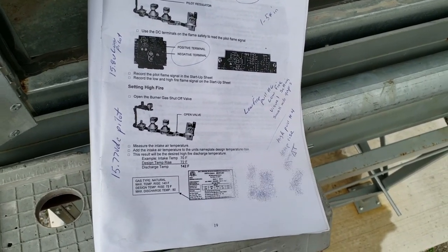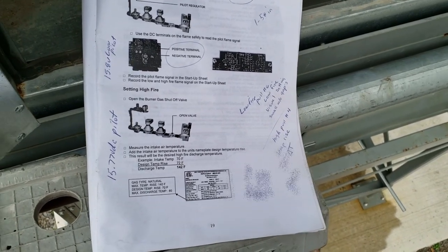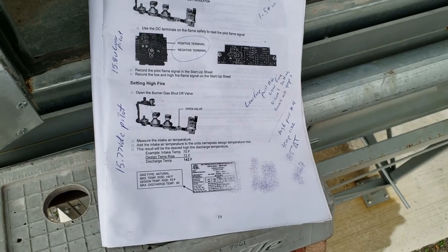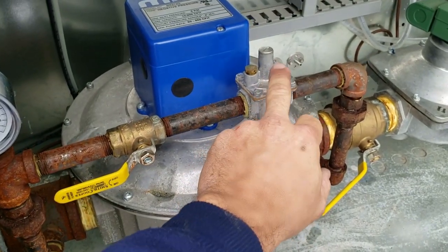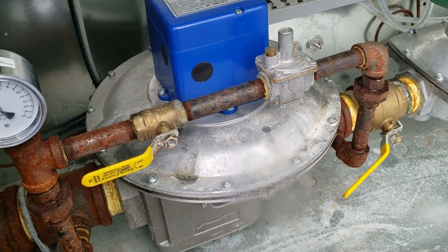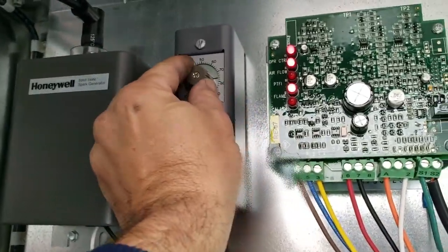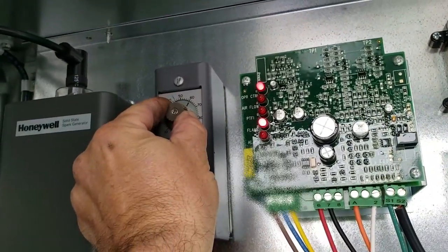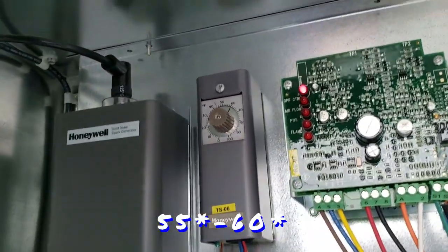So it's getting 70 degree air output even though it's turned all the way down. So you're going to have a little bit of something there. The bypass valve here is what's actually letting it through, and I've got it backed out as far as it can go. So a lot of times that's reason why you'll lock them out depending on your specifications until it's at least a certain temperature outside, which around here I believe it's right around 60. So anything above 60 it won't even run, just the fan only, and the heaters will stay off.